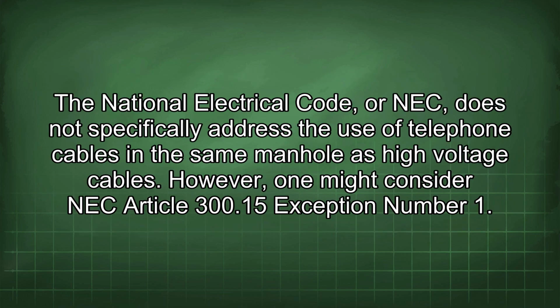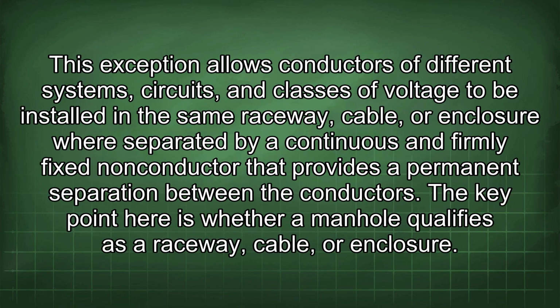The National Electrical Code, or NEC, does not specifically address the use of telephone cables in the same manhole as high voltage cables. However, one might consider NEC Article 300.15 exception number 1. This exception allows conductors of different systems, circuits, and classes of voltage to be installed in the same raceway, cable, or enclosure where separated by a continuous and firmly fixed non-conductor that provides a permanent separation between the conductors. The key point here is whether a manhole qualifies as a raceway, cable, or enclosure.